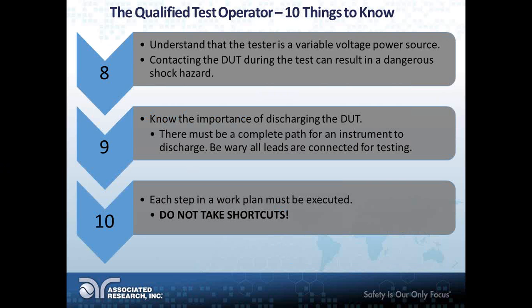I don't care how good the technology is, it's just a physics thing. So you've got to always make sure that your leads are properly attached. There are things you can do on the instrument to make sure that's the case, like making sure you set a low limit parameter, for example, as a leakage limit.